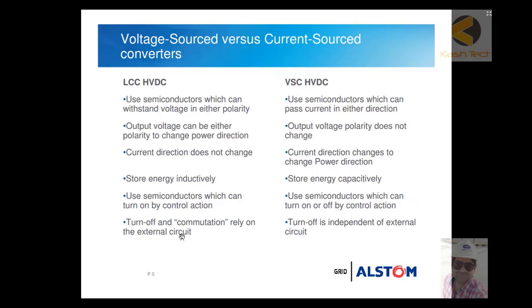Further comparisons: LCC converters use semiconductors which can withstand voltage in either polarity, whereas VSC HVDC uses semiconductors which can pass current in either direction. For VSC HVDC, to change power direction you change the current direction, not the voltage polarity. For LCC HVDC, the output voltage polarity changes to reverse power, whereas in VSC HVDC the output voltage polarity does not change. In LCC HVDC, current direction does not change, whereas in VSC HVDC the current direction changes to change power direction.